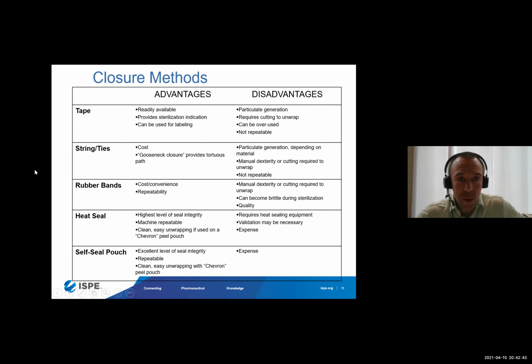The next one here are strings or ties. These could be loose, not integrated into the bag itself. I would say that the preferred method is to have an integrated drawstring. There's a closure method which we call the gooseneck closure, which provides a tortuous path. So this is basically a way to secure a bag with an integrated drawstring, not allowing for any microbial ingress. So really, that's what we're going to focus on, probably the difference of using tape with different cellulose materials compared to strings or ties, drawstrings. I think the polyolefin lends itself to the strings or ties versus the cellulose material typically uses tape.